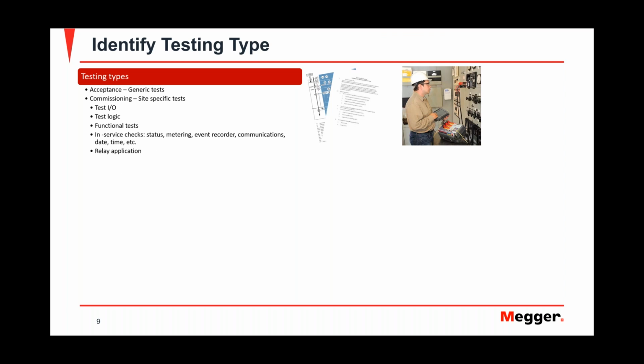Another type of testing that you would have to do is commissioning testing, and these are site-specific tests. This is probably the most important and most stringent test that not only the relay, but your whole protection scheme, the whole application that you're testing, will have to go through. You would have to test not only that the IO works, but the logic, the test logic, and the functional test of your breaker, your motor, your transfer scheme, so that everything works together. It's a system view and a system test, not only a relay test. You would check your status, your metering, the event recorder, the communications, date and times, everything is set up and ready to go, and you'll have a full system test.